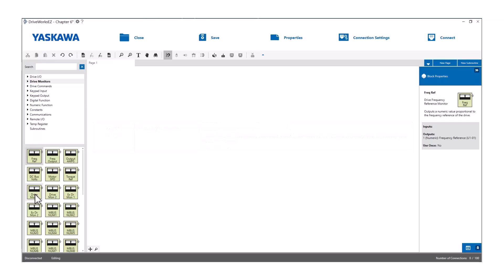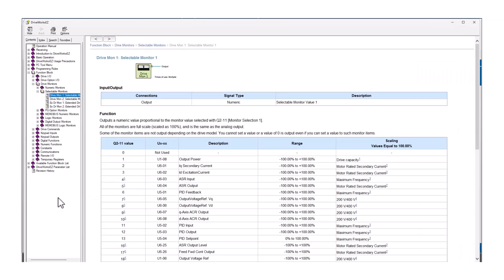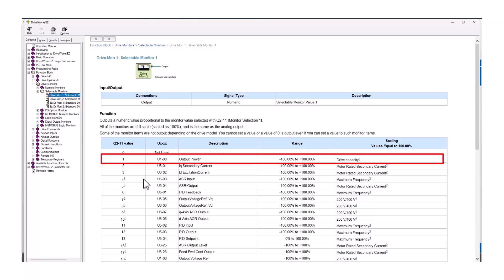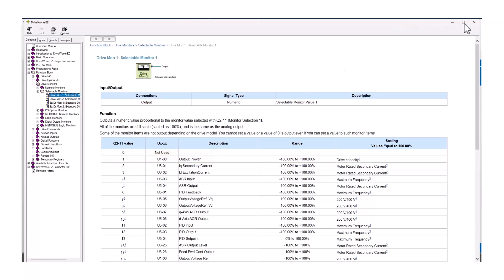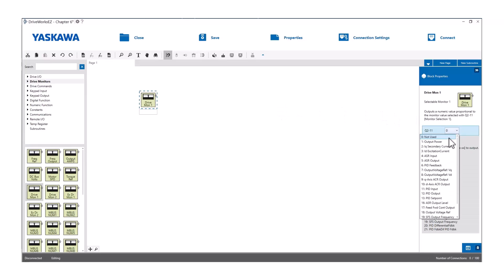A couple of the blocks that are different are the drive mon1 and drive mon2 blocks. These blocks can be assigned to output a numerical value which is determined by how the block properties are set up. If we right click the drive mon1 block and choose more about, we will have a list detailing that Q2-11 is the parameter adjusted when you write the program to the drive. So let's say you want to try output power — that is monitor U1-08 on the drive, setting 1. Let's drag the drive mon1 onto our canvas and set that property to 1. Now it's going to monitor output power.